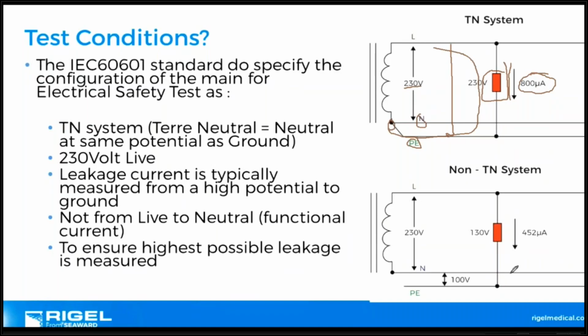If I have an IT system, a non-TN system, the voltage between live and neutral would be mains voltage, but the voltage between live and earth could be, and these are arbitrary figures, 100 volts less, because this isn't connected anymore, so we don't know what this voltage means. This current could be anywhere, but it's going to be less. Therefore, if you test on a non-TN system, your fault current is going to be less than the real fault current. And this is why it's integral to get an understanding of what a TN system is.